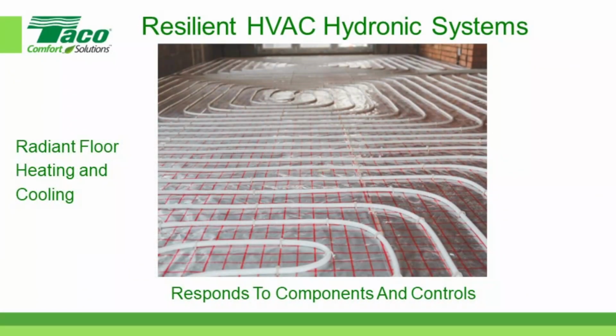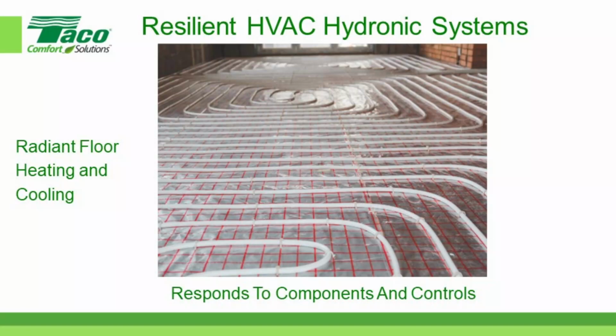Radiant floor for heating and cooling. Radiant floor for heating is very popular, but a lot of people have not had an opportunity to see radiant cooling systems in the floor. They work well in environments that are extremely dry. I think Walmart uses radiant cooling in their floors for some of their facilities that are in places like Phoenix, Arizona. As long as you circulate the water above the dew point temperature inside your radiant system, you can have a radiant cooled building. So some people are doing that. You can see the flexibility that I'm starting to show you regarding hydronic systems.